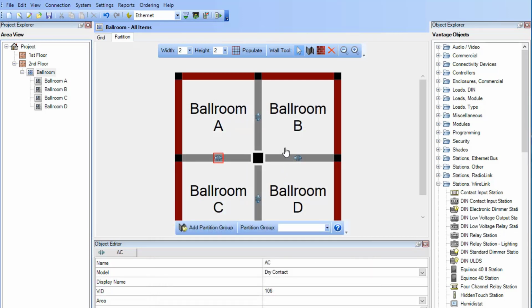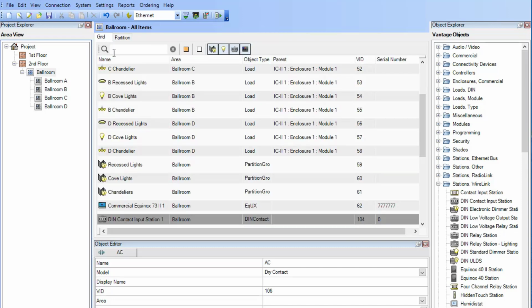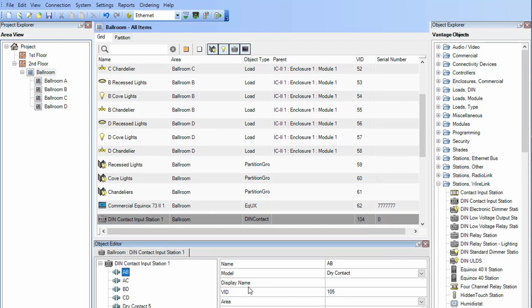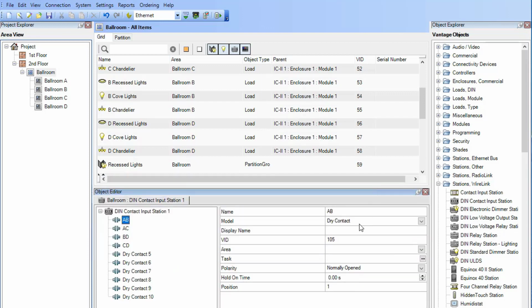Now, in order to make this work with the partition sensor that the Legrand sells, this is an IR sensor, so the contacts close when the beam is complete, and that is when the wall is open. So that's going to be the opposite of what we're typically going to expect. So what we need to do is come into here and we're going to change the polarity.